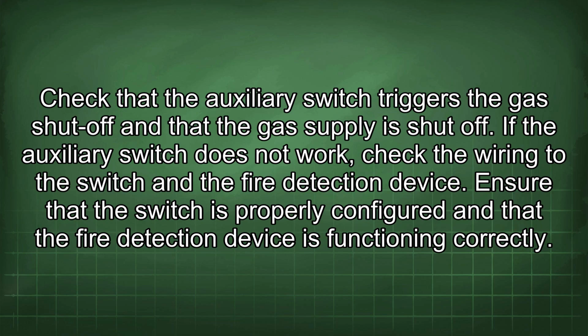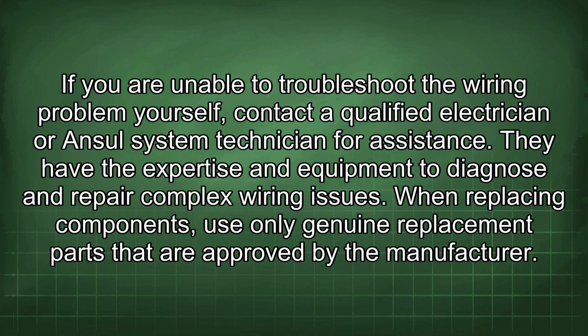If the auxiliary switch does not work, check the wiring to the switch and the fire detection device. Ensure that the switch is properly configured and that the fire detection device is functioning correctly. If you are unable to troubleshoot the wiring problem yourself, contact a qualified electrician or Ansul system technician for assistance. They have the expertise and equipment to diagnose and repair complex wiring issues.